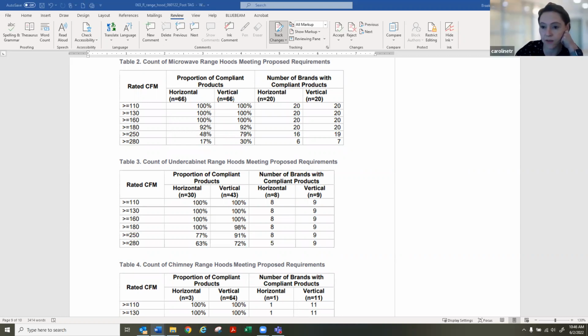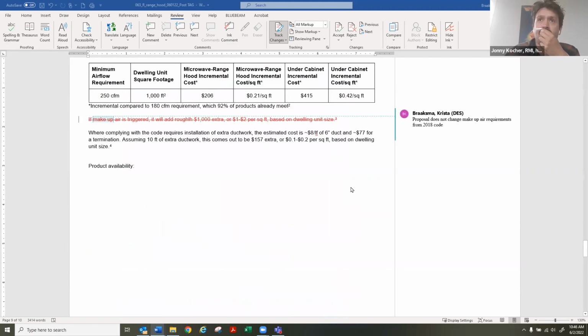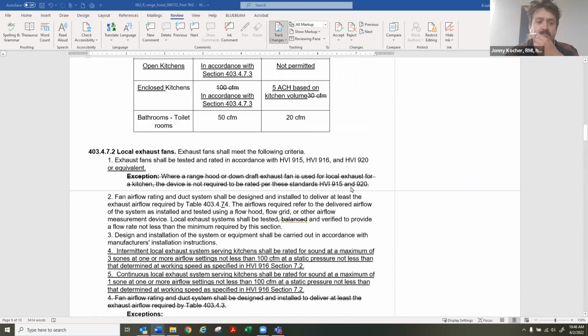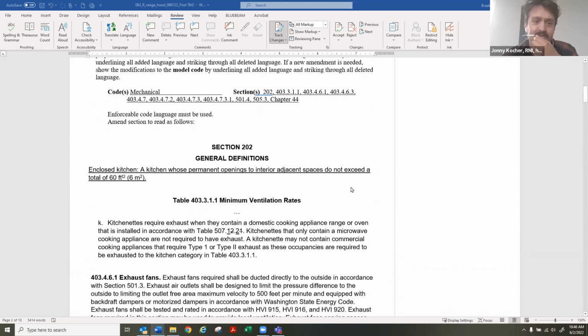Johnny, do you have thoughts about that? Yeah, if people aren't installing enclosed kitchens, they have to install an intermittent exhaust hood at that point. If you don't have an enclosed kitchen, then you basically have an open floor space with a kitchen attached to a living room, and having a continuous exhaust system is kind of meaningless at that point, because the volume of the air is so large that it no longer is doing what it's intended to do, which is to remove pollutants from the space. So, in a 300 square foot apartment, some of these apartments, you can literally touch the stove from the bed, and you're going to require them to install a kitchen hood exhausted to outside. This proposal would require that.